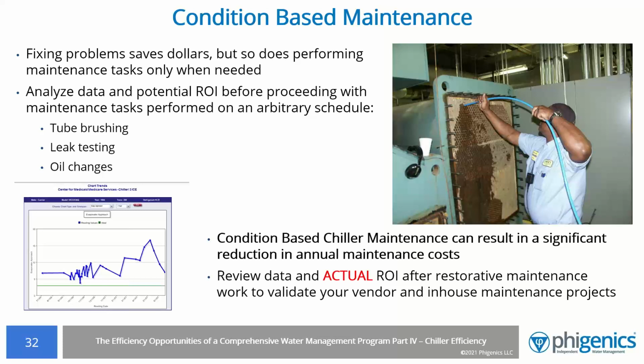Yeah, this is a real close issue for me because we learned a lot about this when we started this a number of years ago at a big university. But in most cases today, maintenance tasking is done on a fixed schedule. If I were to ask everybody how often you brush condenser tubes, you'd probably say we brush them once a year. We do them during the annual maintenance, those types of things. If I were to ask when is the right time to brush tubes, the answer should be they should be brushed when they're dirty and not brushed if they're clean.